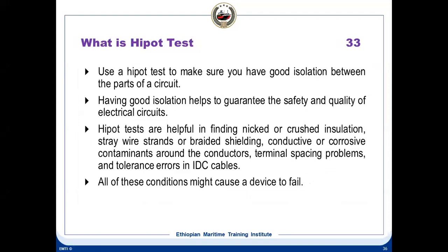Hipot test means it's a high potential test. It is to make sure that you have good isolation between the parts of a conductor. It guarantees the safety and quality of the electrical circuit. It's only for insulation testing, high pot test, high potential test.